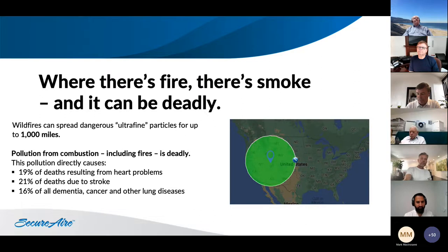At least in that patient tower, for some reason the smoke didn't migrate, and we have filters that remove some of the smoke. But in the emergency department, which is two floors, 100% outside air, that smoke migrated into that space. I walked the whole space during these smoke events. I had two of them while I was there. It was interesting how some spaces—I asked the nurses, 'Do you smell smoke?' And she said, 'Yes.' I couldn't smell it.